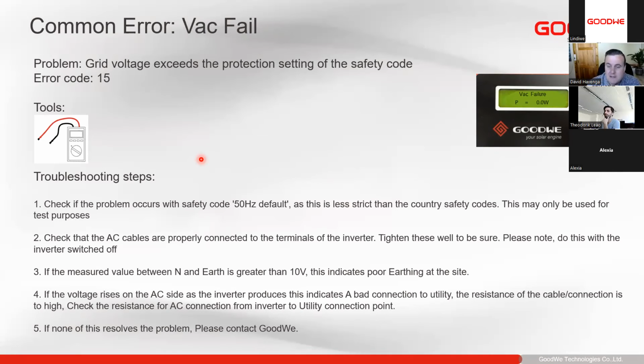If the voltage rises on the AC side, so if the inverter starts to produce, you see it works, then VAC failure, and when you restart it, it does exactly the same. You'll see that the AC voltage is climbing as soon as the inverter starts to produce. That could be because the cable from the inverter to the utility has a high impedance, and that results in a voltage climb on the inverter side, and then the inverter trips off on VAC failure. So as soon as the PV starts producing, you will have an increase of voltage, and that could lead to the inverter switching off on VAC failure. Sometimes it's a bad cable with a bad connection in the cable, which has a higher impedance. And obviously, if none of this resolves the issue, please create a support ticket.